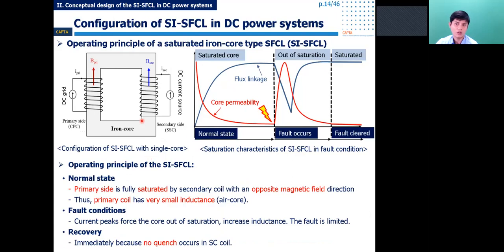Next, I would like to talk about the design configuration of the SI-SFCL. Basically, the SI-SFCL includes one primary copper coil, an iron core, and a secondary superconducting coil. In normal operation, the secondary coil fully saturates the primary side with the opposite magnetic field. So at this time, the inductance is very small because of the air core inductance. When a fault occurs, the current increases very fast, and the core comes out of saturation. So the inductance increases and limits the fault.